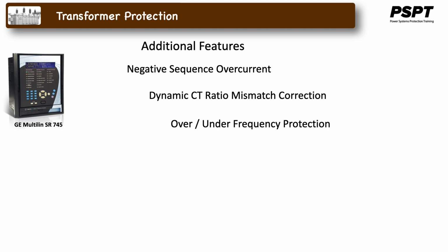For overfrequency and underfrequency protection, the 745 calculates and maintains a running average of the system frequency and the frequency rate of change. Two underfrequency and four rate of change elements are provided to implement traditional and advanced load shedding schemes. Additionally, an overfrequency element can be used to trigger a generator ramp down.